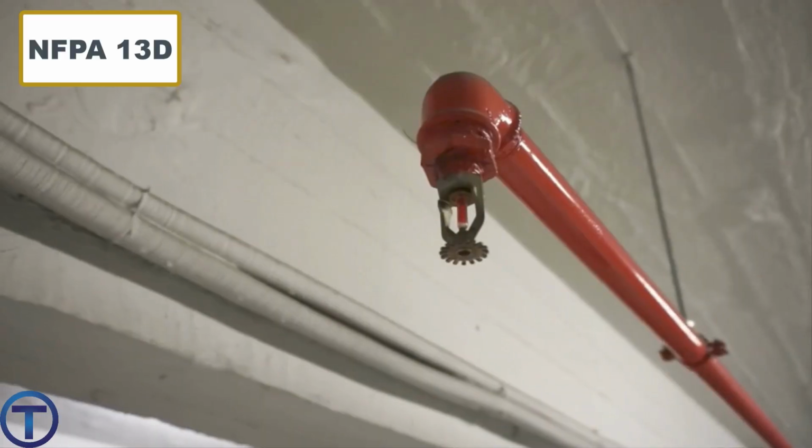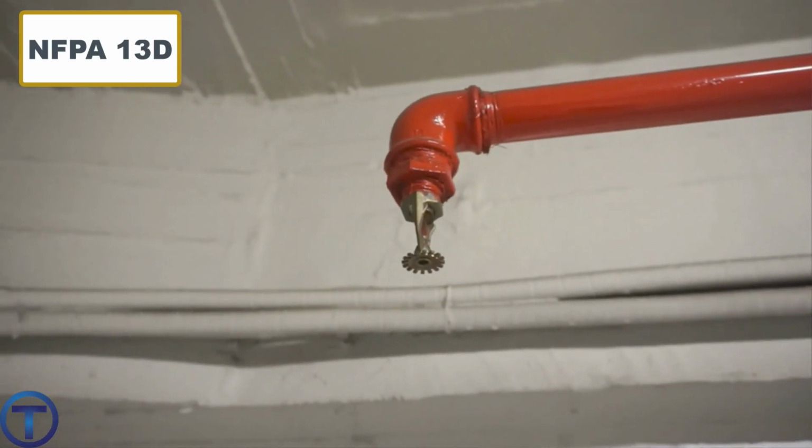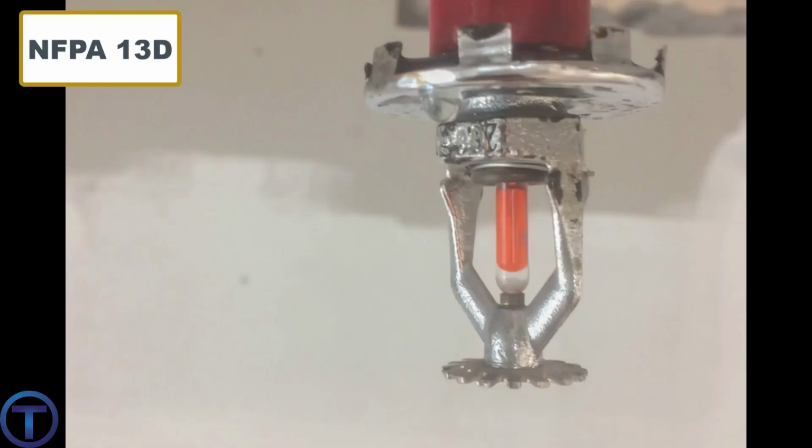Now, in order to understand that, we got to think through this fire suppression system. We have water pipes all through the building with sprinkler heads. Those sprinkler heads we will talk about in depth as we study this. But you need to know up front that they are heat activated. A small vial containing an oil that will rupture when it is heated to a certain temperature is the only thing that holds that sprinkler closed. And when the heat hits the ceiling and it reaches a certain temperature, pop, out comes the water and it puts out the fire. That's the idea.